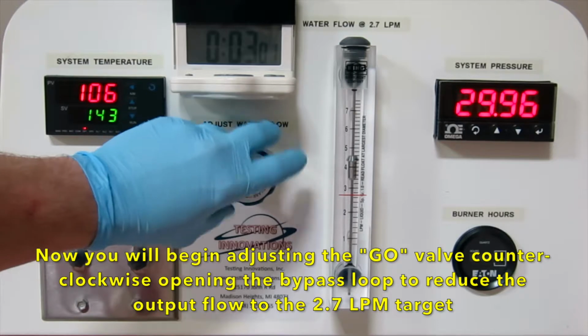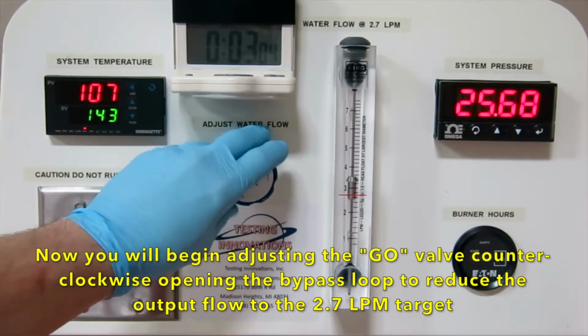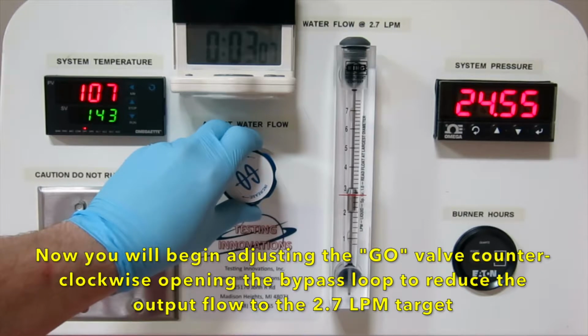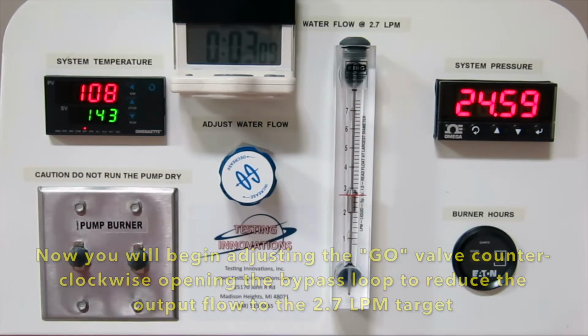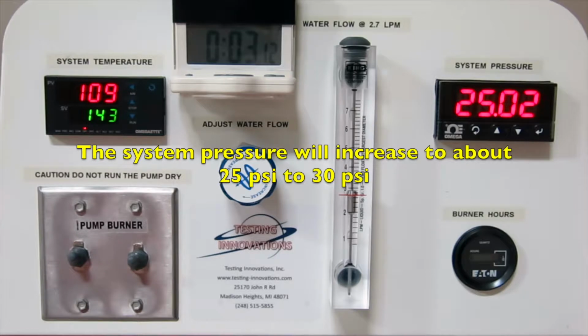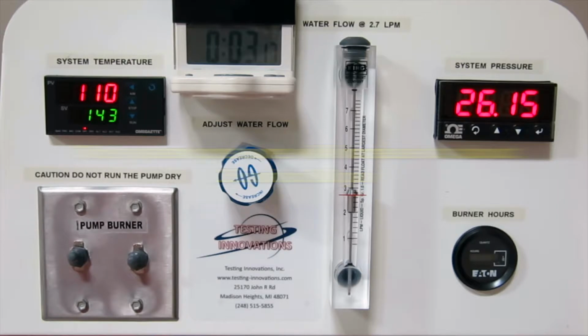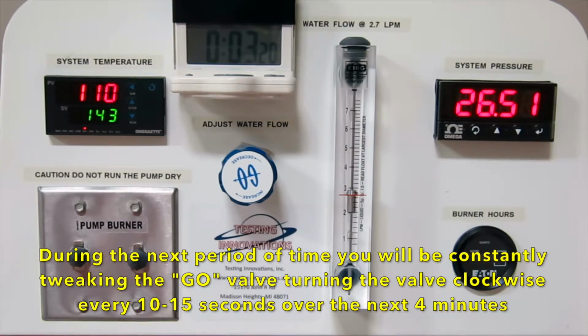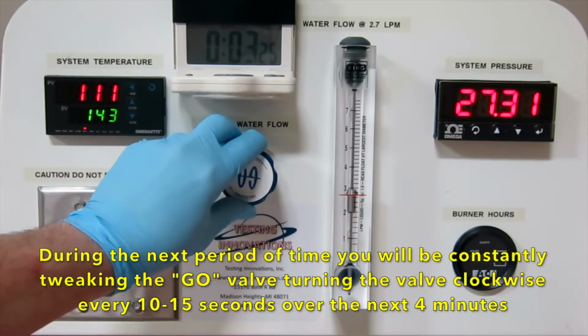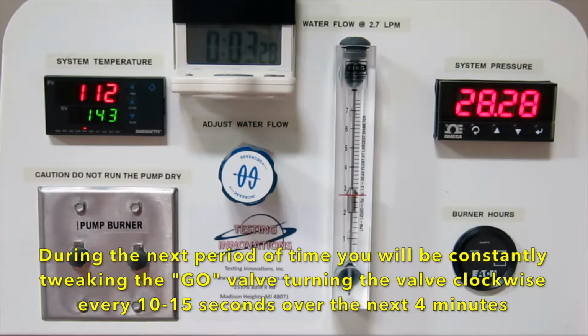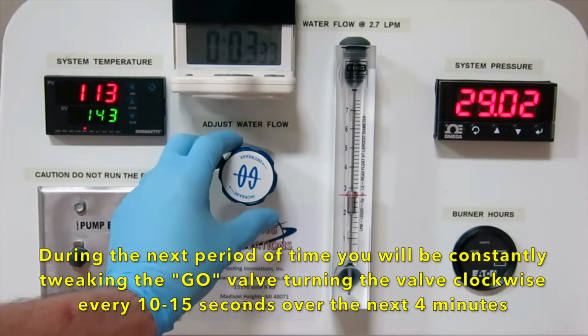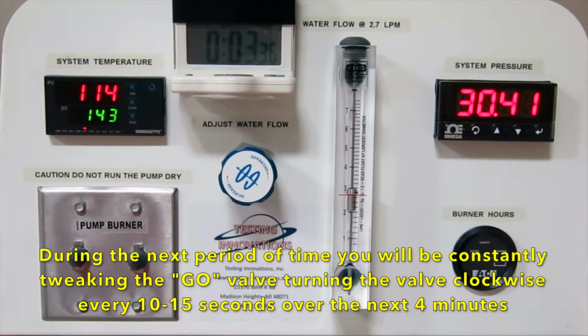Now, you'll begin adjusting the GO valve counterclockwise, opening the bypass loop to reduce the output flow to the 2.7 liters per minute target. You will also see the system pressure increase to about 25 psi to 30 psi. During the next period of time, you will be constantly tweaking the GO valve, turning the valve clockwise, closing down the bypass loop every 10 to 15 seconds over the next 4 minutes, in an effort to maintain the 2.7 liters per minute flow rate. At this stage, you can adjust to slightly below the target line of 2.7 liters per minute. Try adjusting a little at a time.